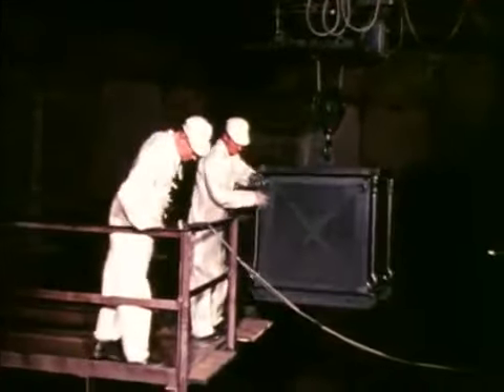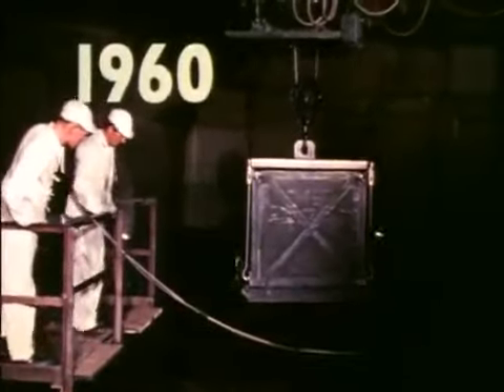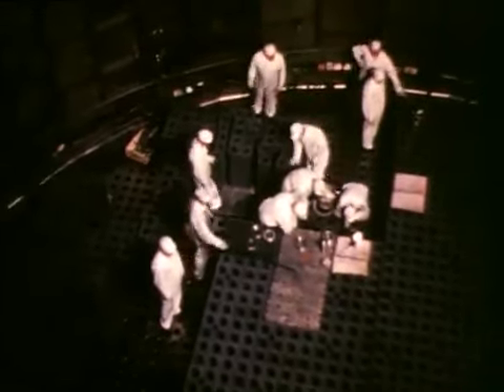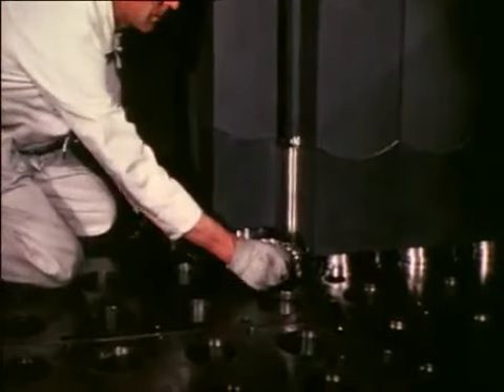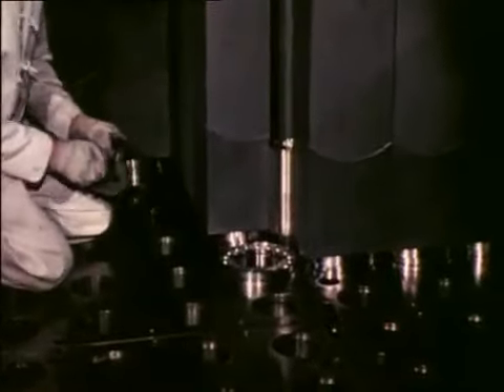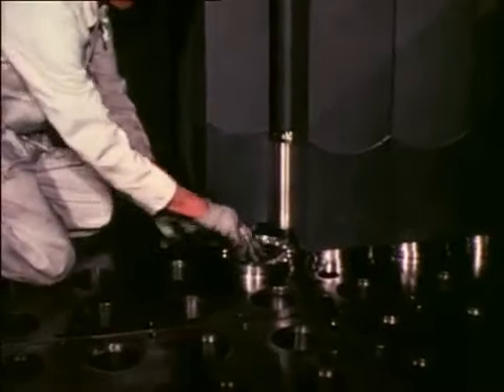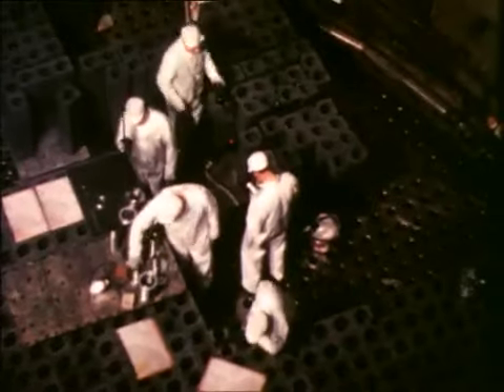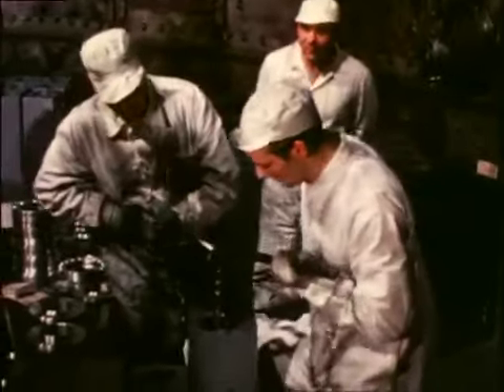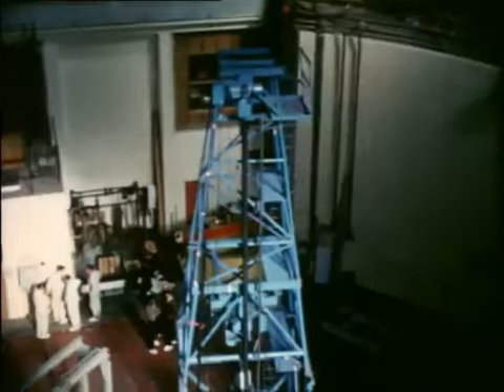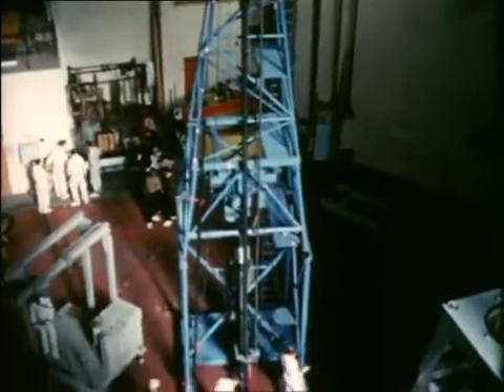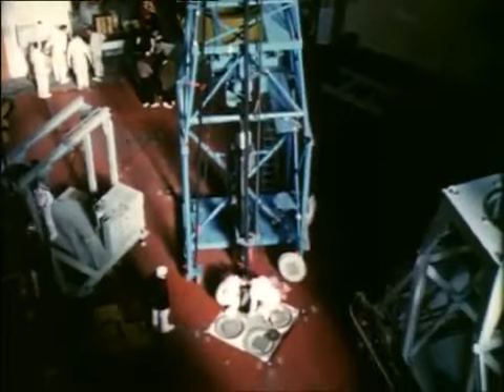The core consists of vertical columns built up from blocks of graphite machined to an accuracy of 5/1000th of an inch. Each column is 30 feet high and is individually supported through a ball bearing assembly on the diagrid. This transmits the weight of the structure to the 18 A-frames under the pressure vessel. The completed core contains over 3,000 fuel and control rod channels.